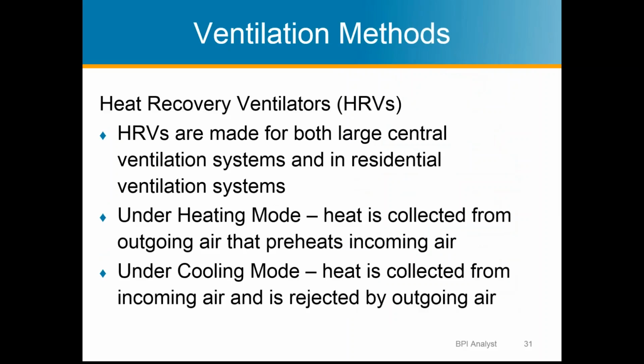HRVs can be large or small. The smaller residential systems are balanced systems. So under the heating mode, when you're heating the house, the cool air comes in, is being supplied to the house, and the heat energy from the air leaving the house is used to heat the air that's coming into the house. Now the 2 air streams don't mix, so you're not mixing any of the air leaving or coming into the house, but the heat is being transferred from the air leaving the house into the air that's coming into the house. So it helps temper that air.